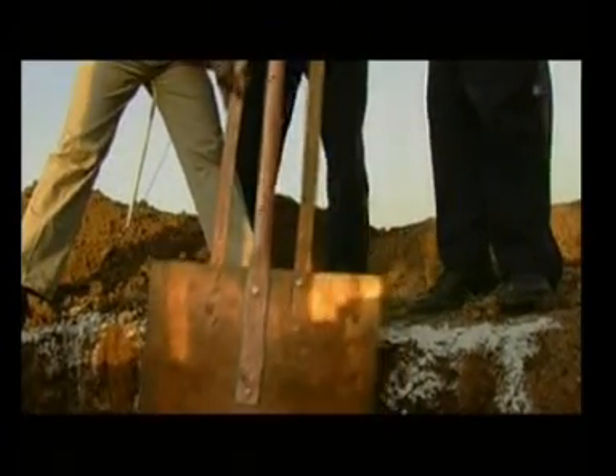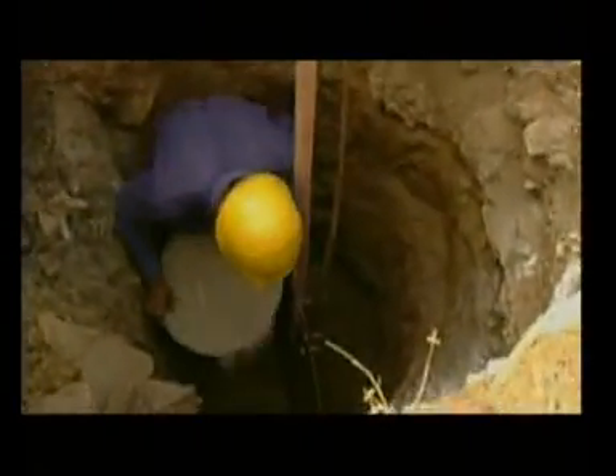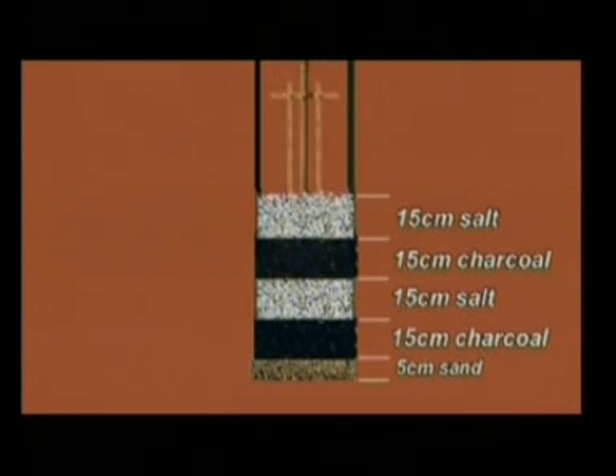Holes are drilled in the copper pipe at various angles, which help in spreading the water and keeping the earth moist. The earth plate is kept upright in the pit and coal, soil and salt are filled in up to 90 centimeters, taking care that the layers of coal and salt are of 15 centimeters each. This lowers the resistance of the earth and results in a better electric flow.